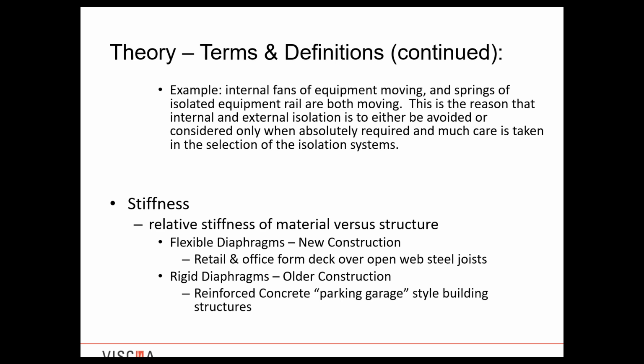So the only thing that would be moving in the equipment would be the cyclic behavior of the fans and motors, but then you would also have the springs and the isolation sheet metal curb or the inertia base that would be moving. So again, 2 degrees of freedom. So stiffness here, and John touched on this a little bit as he was describing different building elevations and different building bays as far as column spacing. But you have relative stiffness of the material versus the structure.